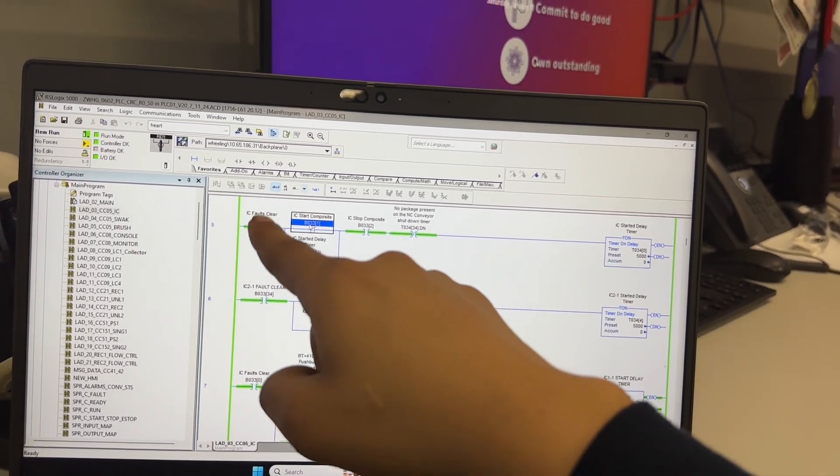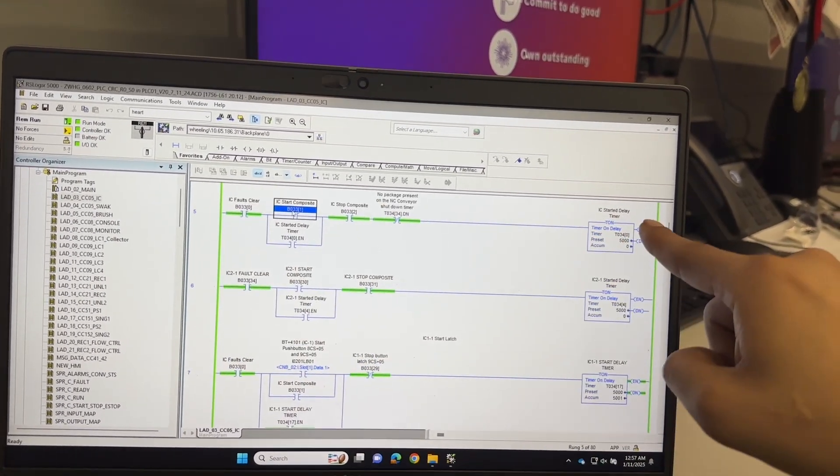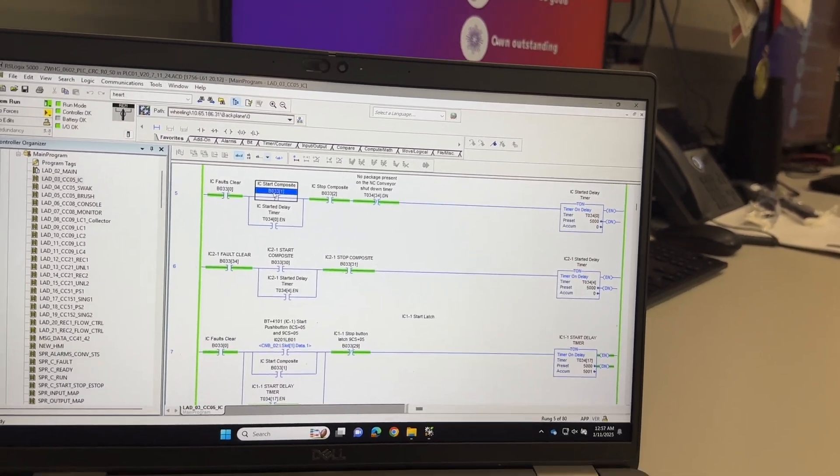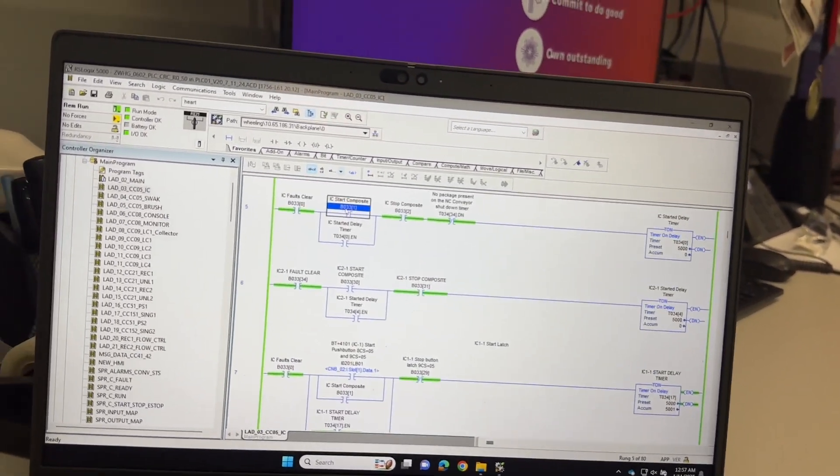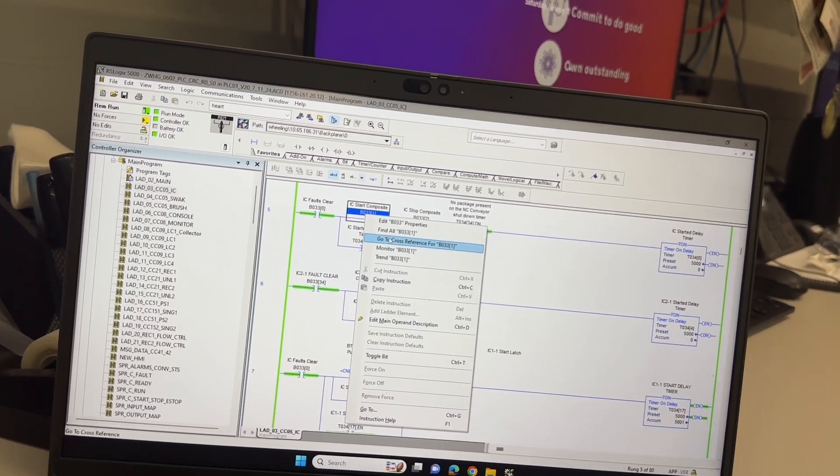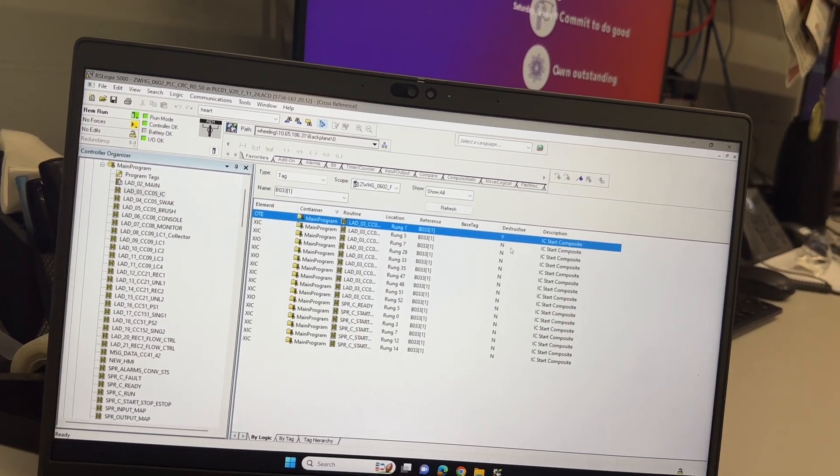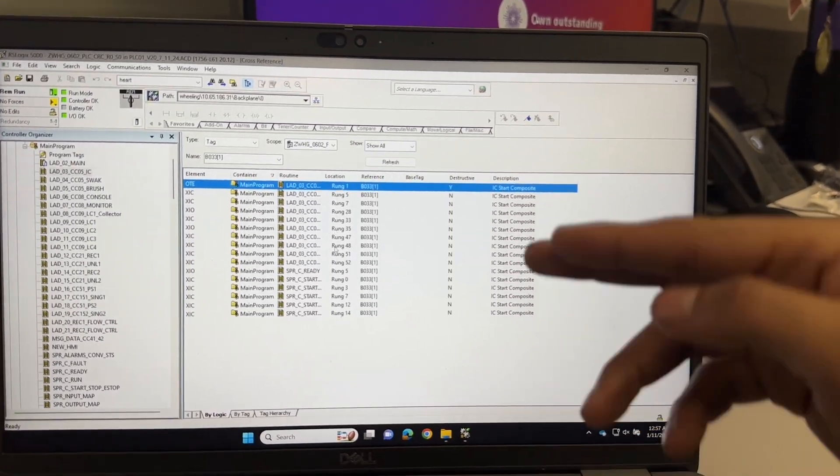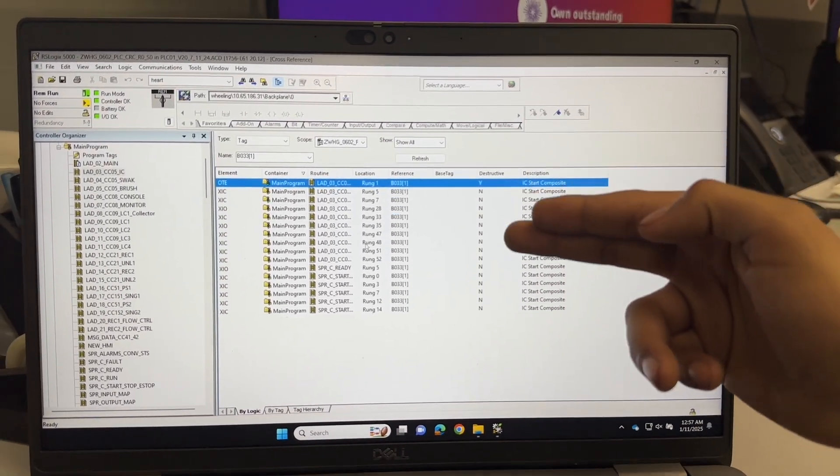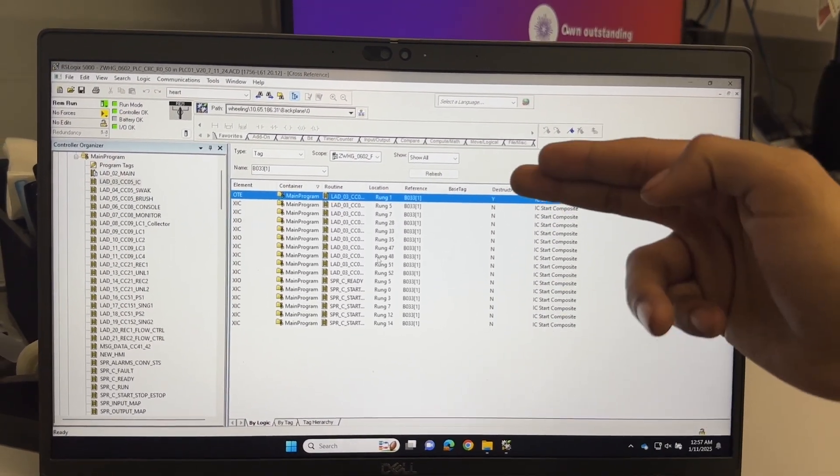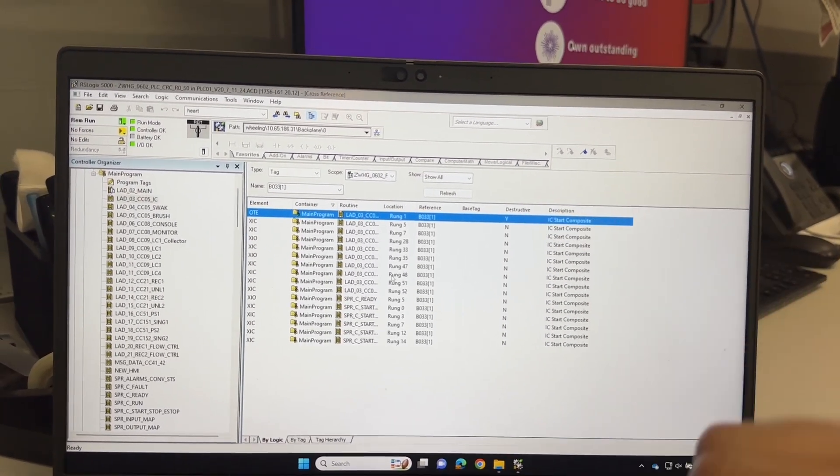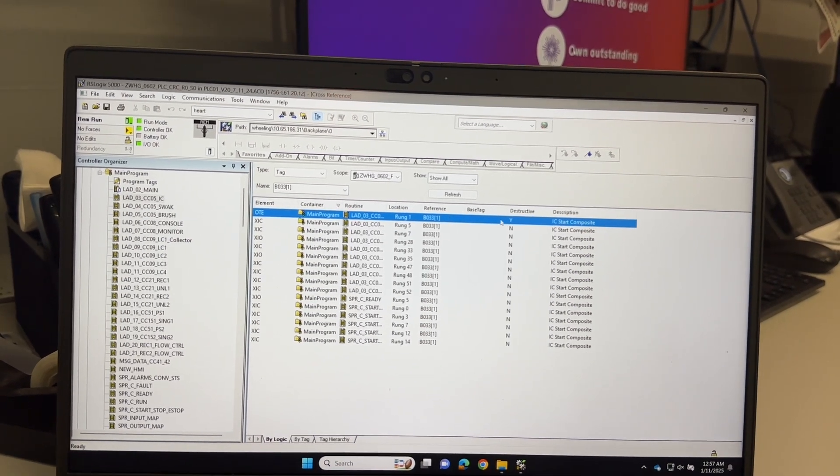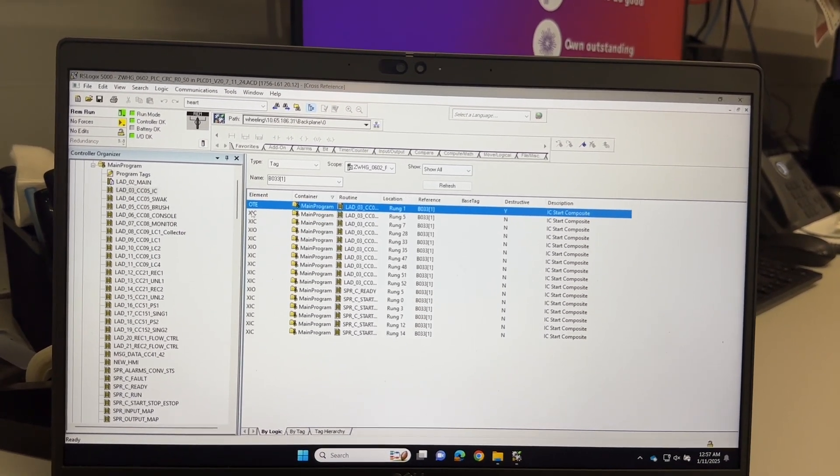If this internal bit is turned on, it will turn on the timer. The enable bit of this timer will then latch on and then turn on that machine after a five second delay. So if I do the same thing again here, go to cross reference, and then the same thing right here. Look, all of them say no for the destructive column and there's one that says yes.